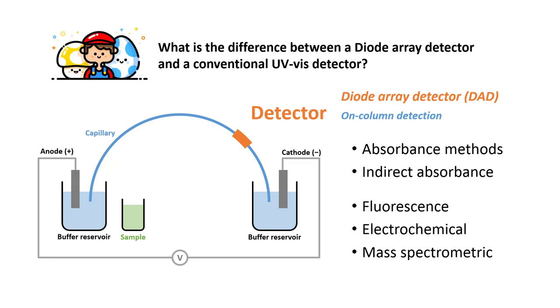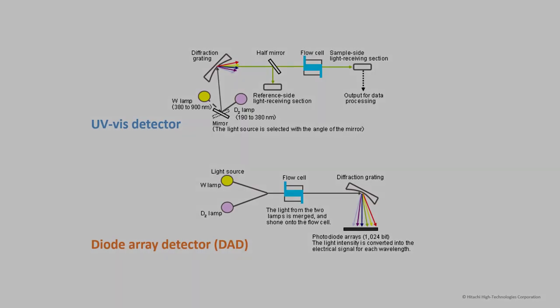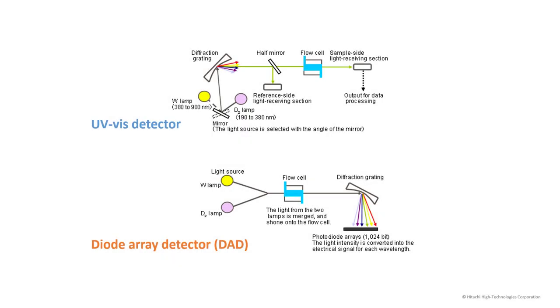What's the difference between a DAD detector and a conventional UV-Vis detector? In short, UV-Vis detector is like UV-Vis spectrometer. It can detect one wavelength at a time, while DAD detector can detect multiple wavelengths at one time. If you are interested in learning more about the DAD detector, do check out the link below.